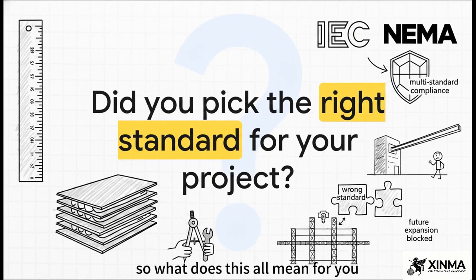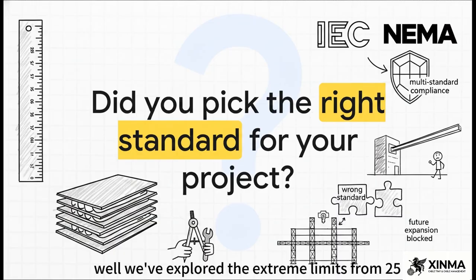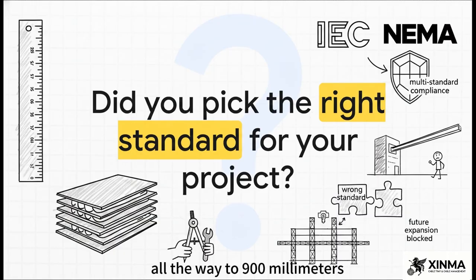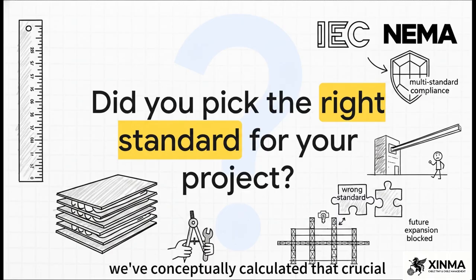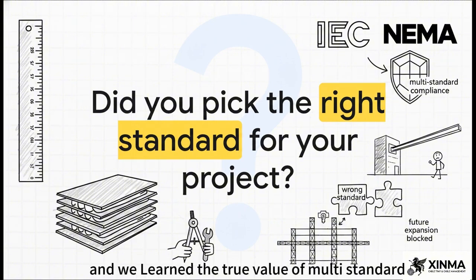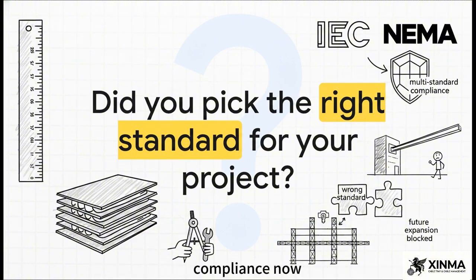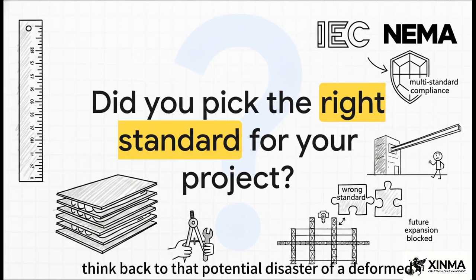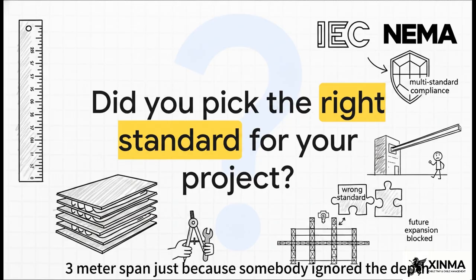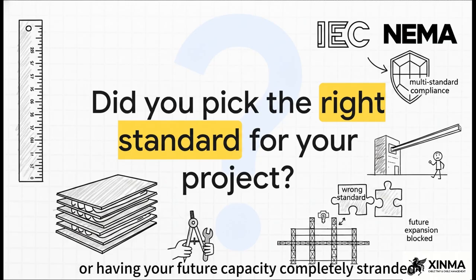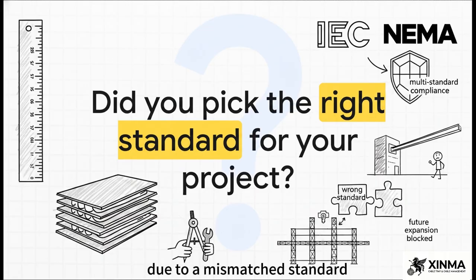So, what does this all mean for you? Well, we've explored the extreme limits from 25 all the way to 900 millimeters. We've conceptually calculated that crucial 40% fill ratio, we contrasted the vital precautions between IEC and NEMA, and we learned the true value of multi-standard compliance. Now, think back to that potential disaster of a deformed 3-meter span just because somebody ignored the depth, or having your future capacity completely stranded due to a mismatched standard.